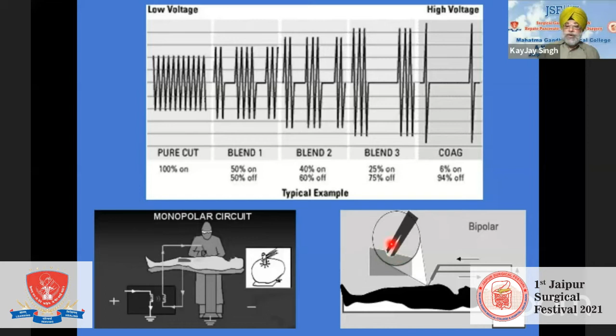Bipolar is a relatively safer option because here the current is not dissipated to the whole of the body. It's only localized to that area of application, going through one prong and getting out through the other. So we need to know how it can fail. The first way the electrosurgical unit can fail is unintended direct application of the hot tip to tissues. That may happen in momentary diversion of surgical attention away from the surgical procedure. Maybe the anesthetist is telling you something, or maybe you are receiving a call, which ideally you should not, but in the private sector it happens that the mobile of the surgeon is never usually off.